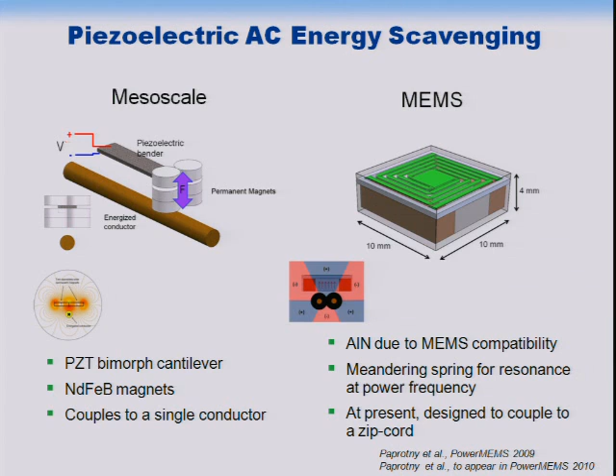This also shows that the system is designed to work with a zip cord. On a zip cord, the problem is that you have the power and the returning power next to each other, a loop where two conductors sit side by side. If you use a current transformer on that, the magnetic field actually cancels out, so you can't get a decent measurement. Our system, however, is able to harvest power from that.